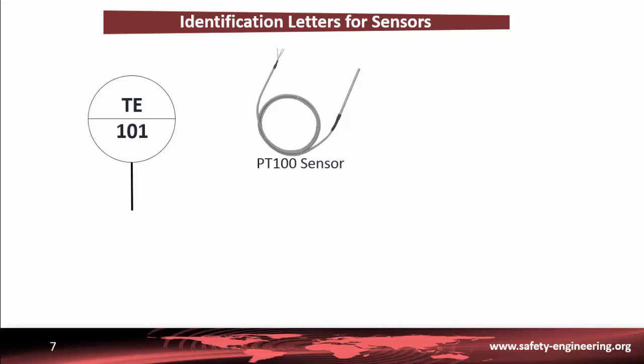A classic example is the PT100 sensor for measuring temperature. The primary element is the sensor alone — just the PT100 — and the output of this sensor is the resistance as a function of temperature. The symbol associated with this sensor is TE: T for temperature and E for primary element.